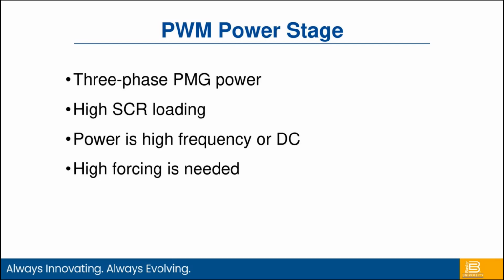Likewise with the frequency, we can handle a high frequency, or we can even handle a DC input if a customer wants to put a battery input into the power input rather than an AC waveform. It also gives us the opportunity for high field forcing. So if you think about that power stage that we just looked at, we're rectifying all the AC, and that capacitor has the ability, minus any losses, of course, to charge that cap up to the peak voltage point. So it gives us a lot more overhead and a lot more forcing in instances where we need a high forcing reaction to maybe heavy load currents or fault currents.